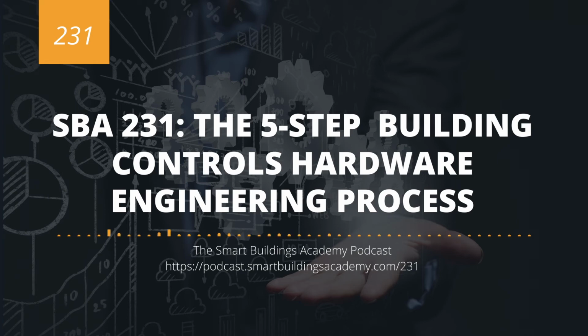So if you have a terminal unit with 1-stage reheat, and then a terminal unit with 2-stage reheat, and a cooling-only terminal unit, you would have 3 system types. You may have 100 boxes, but you would have 3 system types. Now, if you come along one of those cooling-only boxes that has an alternate humidity sensor as well, then that becomes its own system type as well. So you kind of see what we're looking to do here is we're looking to build our kits.